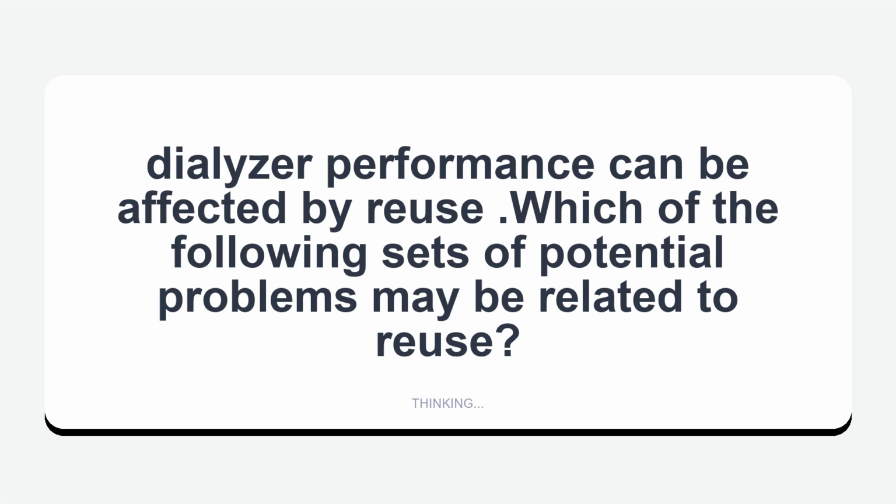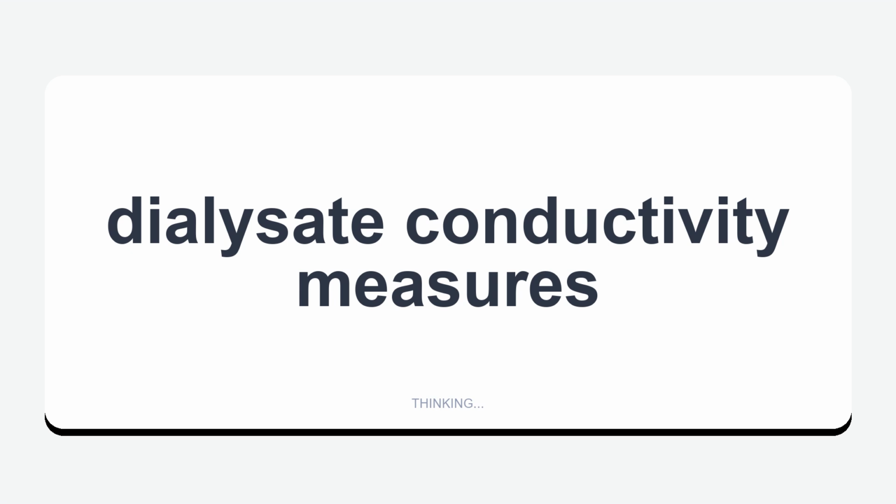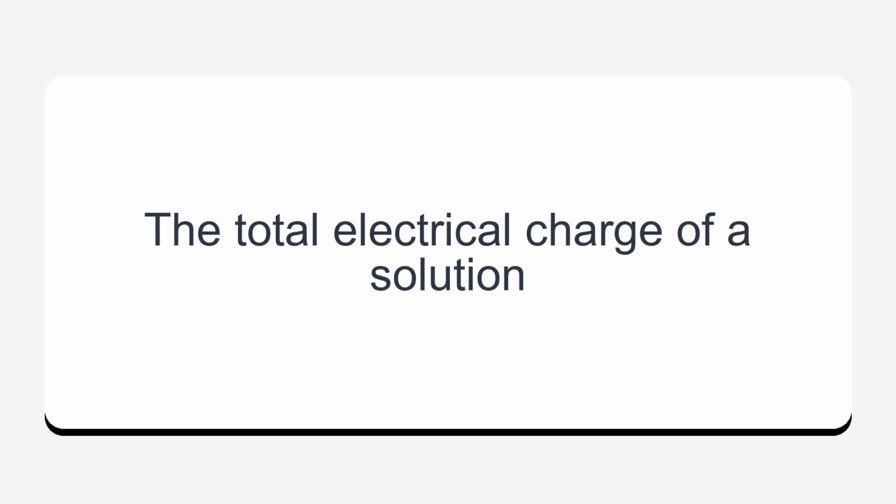Dialyzer performance can be affected by reuse. Which of the following sets of potential problems may be related to reuse? Blood leak, first-use syndrome, inconsistent ultrafiltration. Dialysate conductivity measures the total electrical charge of a solution.